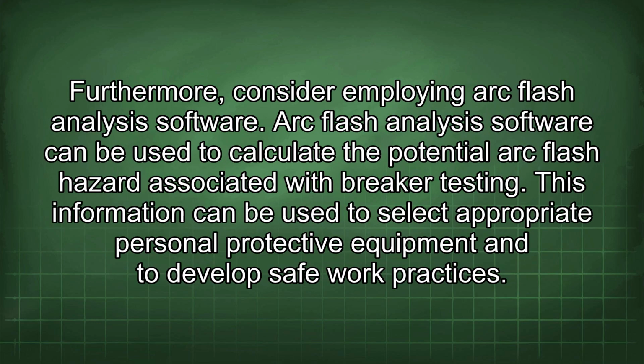Furthermore, consider employing arc flash analysis software. Arc flash analysis software can be used to calculate the potential arc flash hazard associated with breaker testing. This information can be used to select appropriate personal protective equipment and to develop safe work practices.